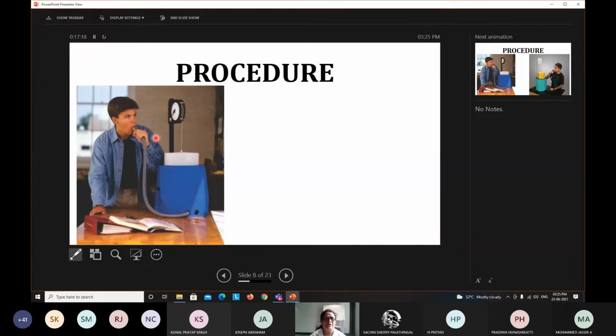That is one recording. When he is blowing out, the air goes through this and the bell will move. Accordingly, the circular disc will move and the needle over this will also move and show the reading, which is marked in ml. You can convert them into liters also. So note down the recording. This is done when the person is in standing position. So this instruction has to be properly given.